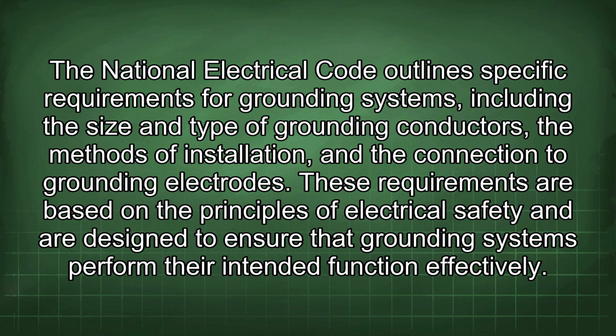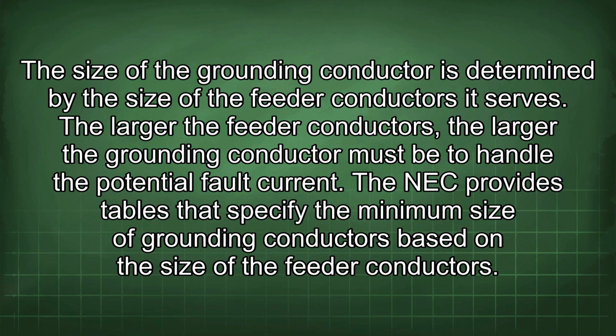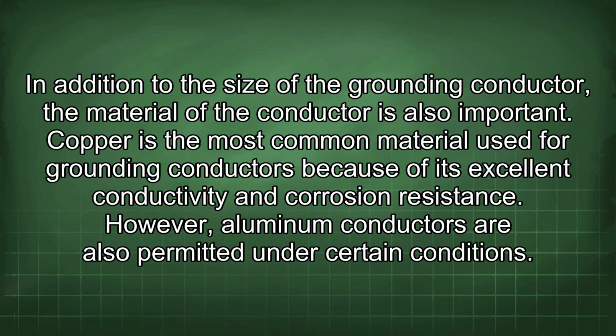intended function effectively. The size of the grounding conductor is determined by the size of the feeder conductors it serves. The larger the feeder conductors, the larger the grounding conductor must be to handle the potential fault current. The NEC provides tables that specify the minimum size of grounding conductors based on the size of the feeder conductors. In addition to the size of the grounding conductor, the material of the conductor is also important. Copper is the most common material used for grounding conductors because of its excellent conductivity and corrosion resistance. However, aluminum conductors are also permitted under certain conditions.